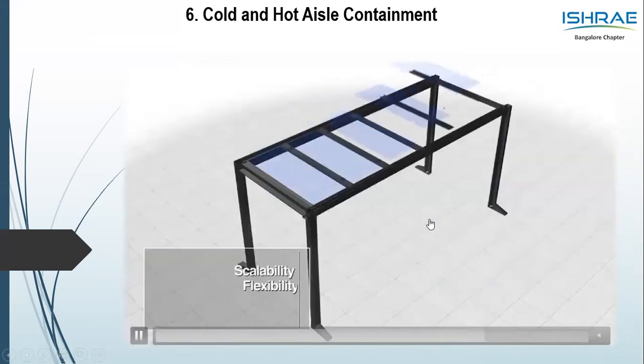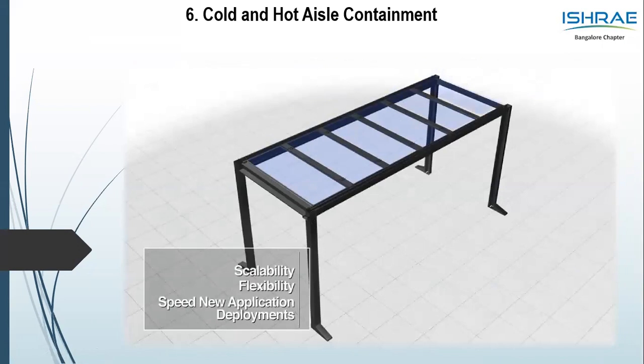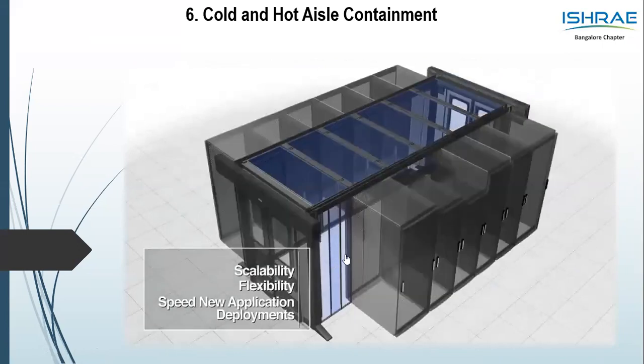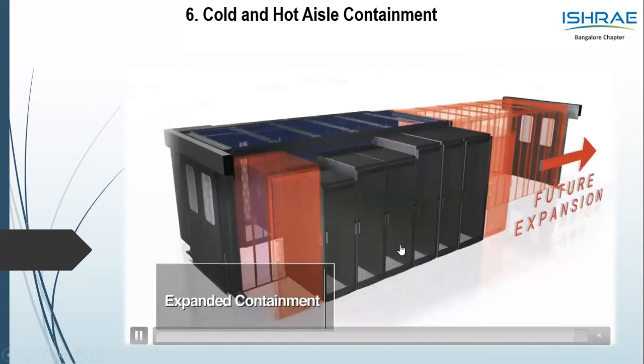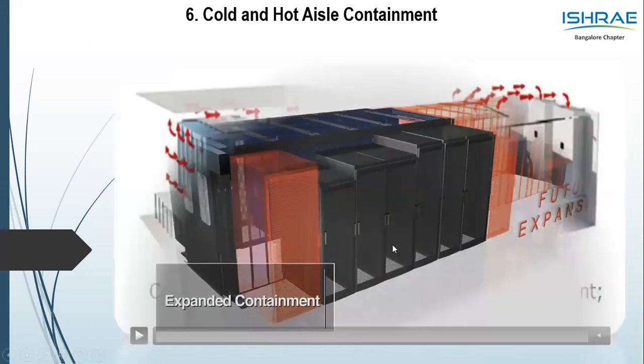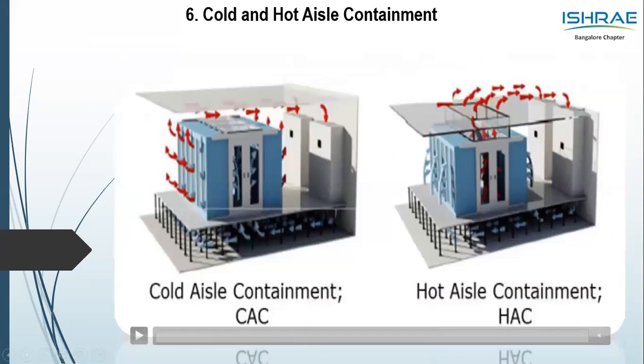All these are customized, built as per every site, every rack and server and the cooling unit. This can also be scalable considering the future expansion of the data center. So as long as you do a containment, it is very good. There are two types of containment, cold aisle containment and hot aisle containment. In hot aisle containment, the hot air is contained; in cold aisle containment, the cold air is contained. And just to give you a quick pros and cons on the hot aisle containment, you have this plenum, thereby your capital cost may increase. Again, the hot aisle is recommended where you have high return air temperature and when you use different cooling units.